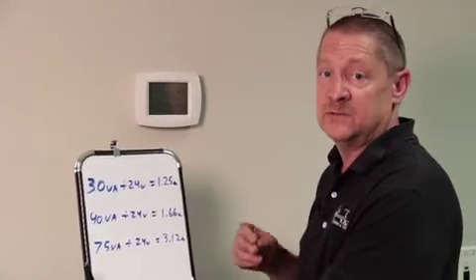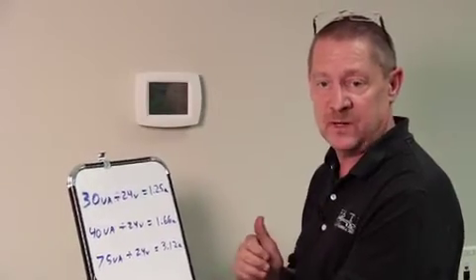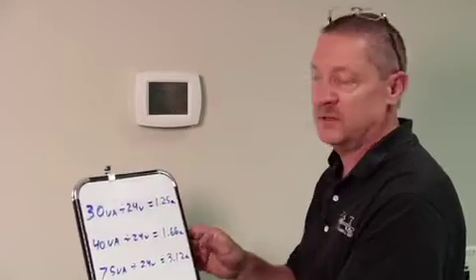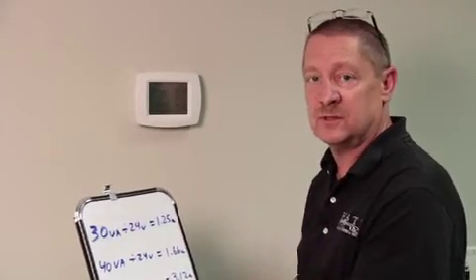In those issues we're going to want to put in a push button reset transformer and come to the thermostat location and energize one circuit at a time, try to figure out which circuit has given us that overload condition.